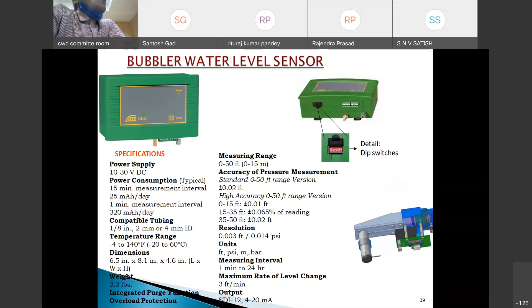So how we are getting the measurement is, we measure the tube pressure, compare with the old pressure value, and determine the amount needed to pump in cycles. Then we have an atmospheric pressure reference measurement. Then pump and bubble out, and measure the actual tube pressure. So this calculation will provide you what is the pressure of the water. So this can be changed into water level by having a calibration equation.